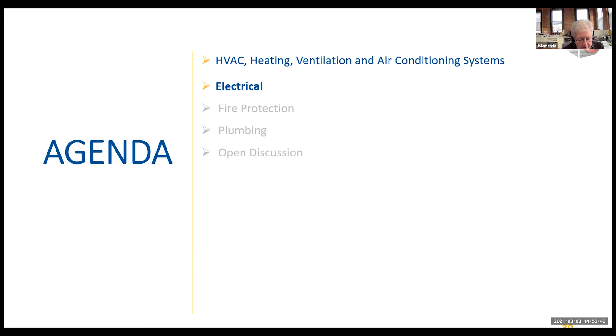In summary, the electrical systems are actually in fair condition. We went through, looked at electric rooms, checked out the generator, wiring methods, things like that. Everything seems code compliant, in fair condition. There's an 800 amp service, 480 volt, meaning none of the options or additions would require a service upgrade that I can see. 800 amps at 480 volts is 12 to 13 watts a square foot, so that seems okay, and there's plenty of adequate capacity in those distribution panels.